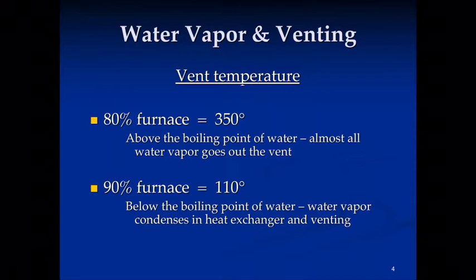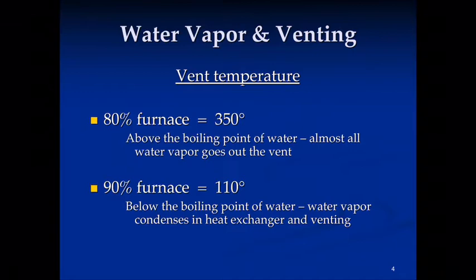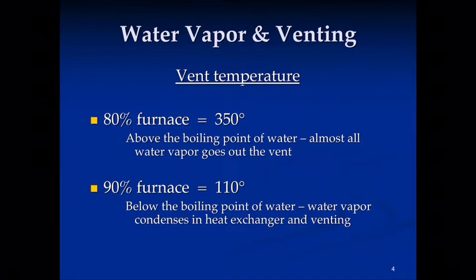Let's look at some typical temperatures we might deal with. On an 80% efficient furnace — whether it's 80, 81, 82, 83% and so on — flue gas temps are going to be somewhere in the 300 to 400 degree range, so roughly 350 degrees. Almost all of that water vapor should be going out the vent; there should be very little left that would not be exiting the vent system.